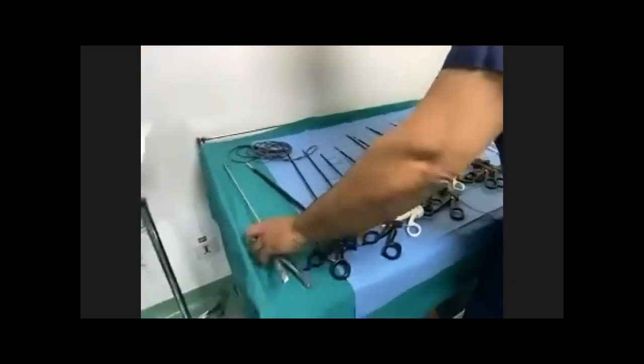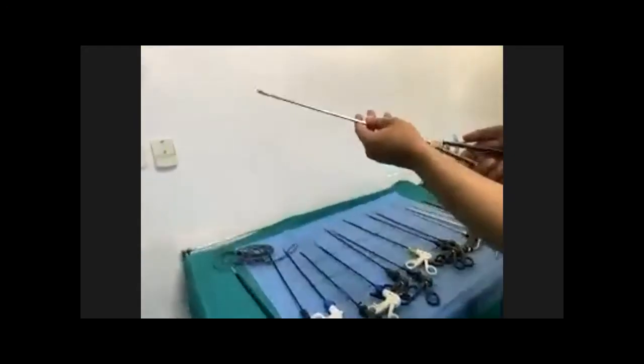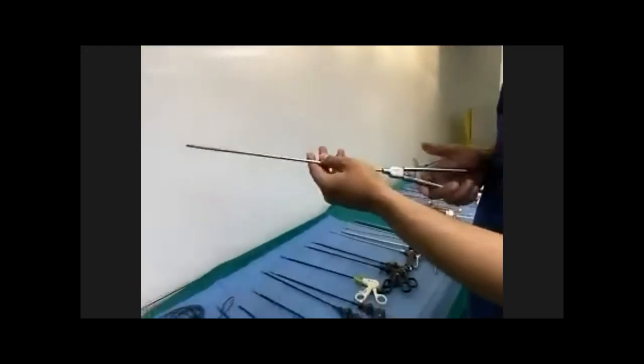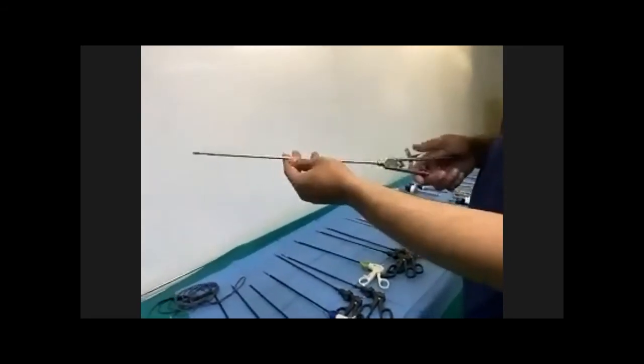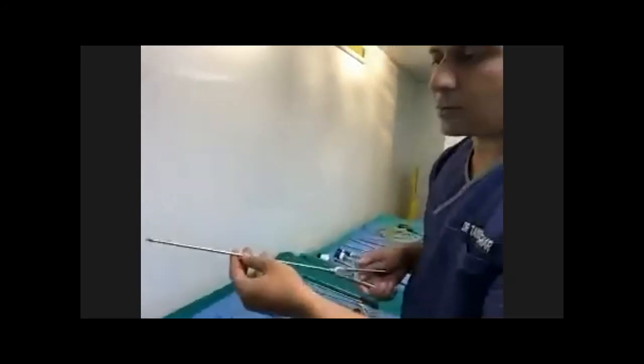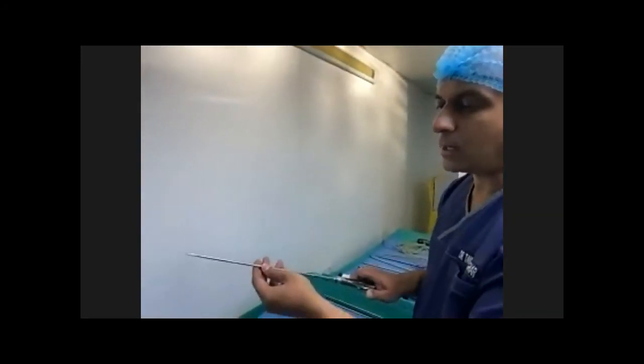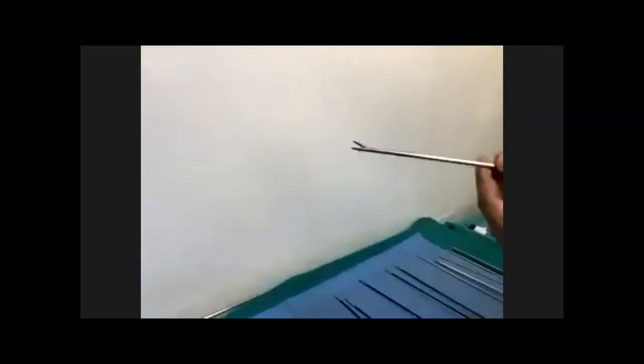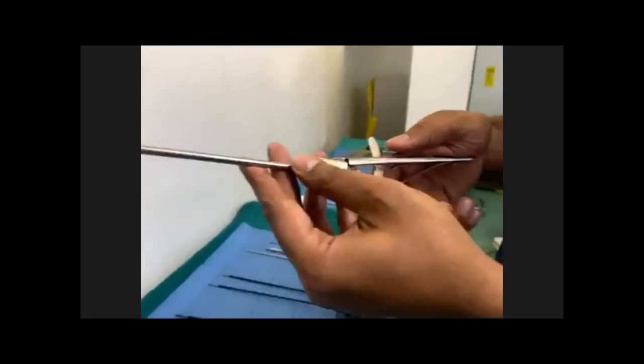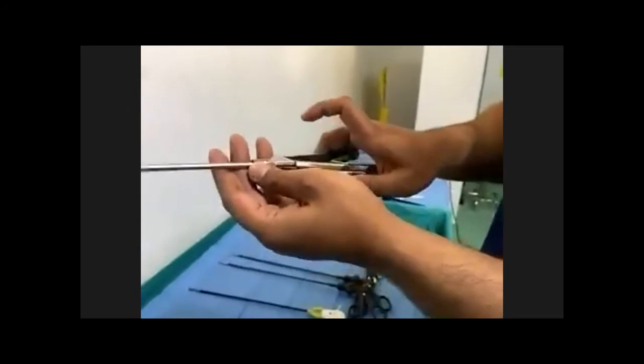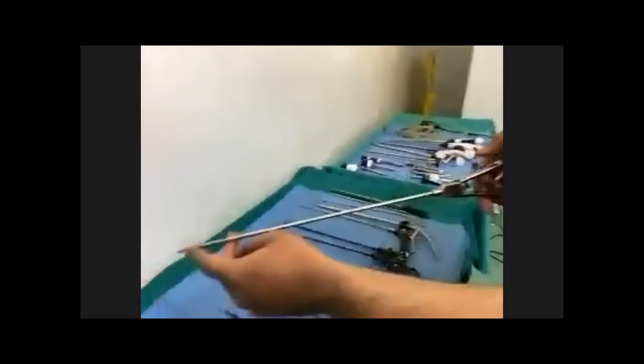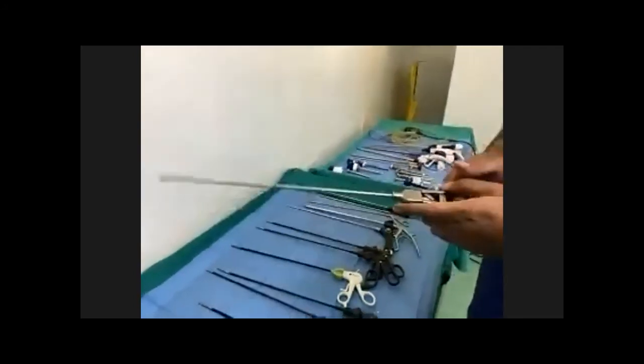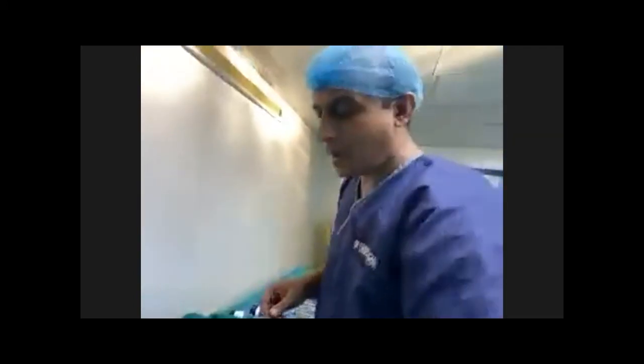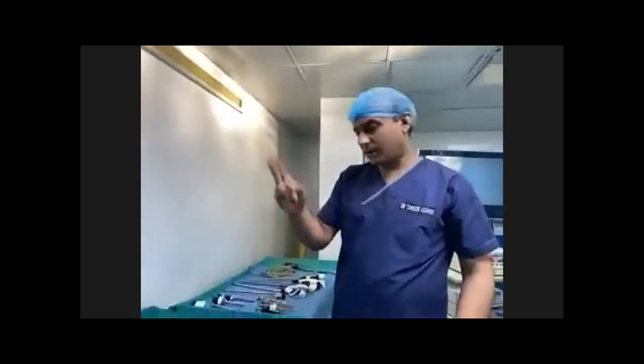Okay. Now, this is another important instrument which is usually used in advanced laparoscopy, because in basic laparoscopy you are not so good at intracorporeal suturing and knotting. This is a needle holder, endo needle holder. You can see they are of different types, right? This is the shaft. This is the lock, and you can unlock it by pressing it like this. So you mount a needle over it and start suturing.